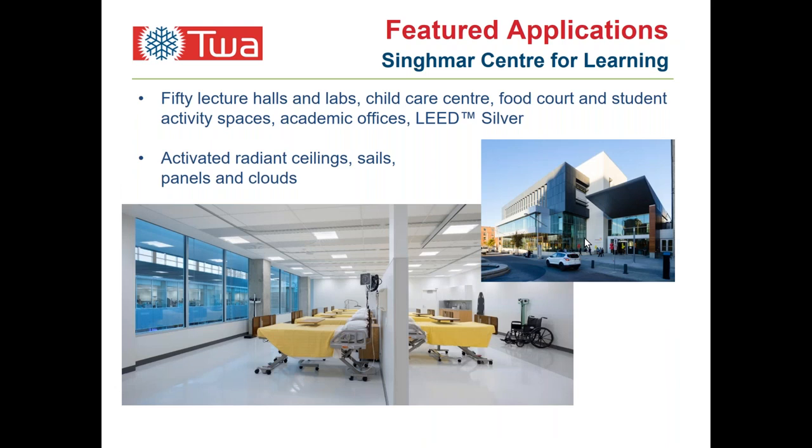This is a teaching facility where the panels are in immovable positions where the curtain tracks are. To lower the installation capital cost, conventional acoustic ceiling tiles were placed in the grid outside of the immovable pieces, just to manage the budget. Radiant was very popular in the 1960s in VA hospitals, although it struggled then because of building envelopes and controls not being up to today's standards. With tighter envelopes and tighter controls, radiant is making a resurgence — particularly for managing occupant comfort and acoustics.